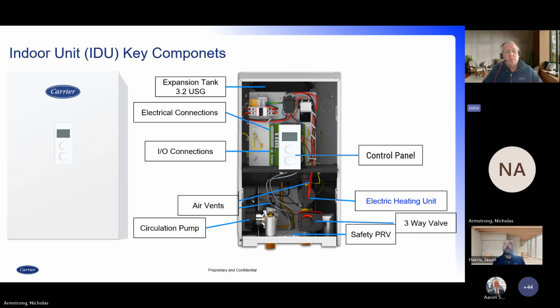And it provides up to about 20 to 30,000 BTUs of backup heat, either for domestic hot water or for heating. And this is programmable as well. You can tell the indoor unit that at a certain outdoor temperature, I'm not going to be providing enough energy output to either adequately heat or warm up the domestic hot water, so I want to bring my backup coils in to supplement that heat. And all that is done on the control panel. It's a white interface control panel with a scroll-through type menu structure. Okay, next slide.